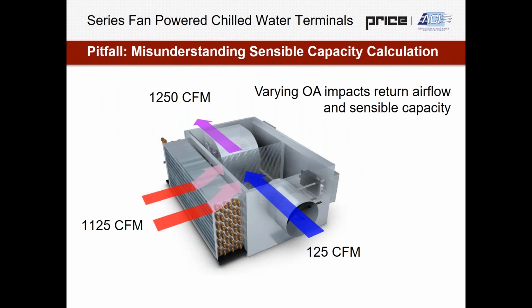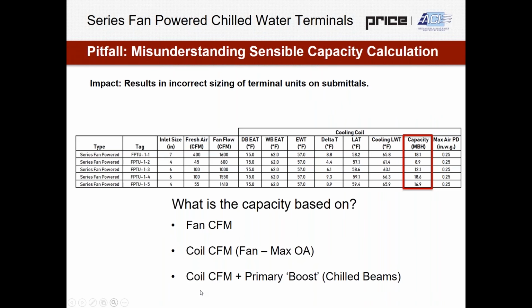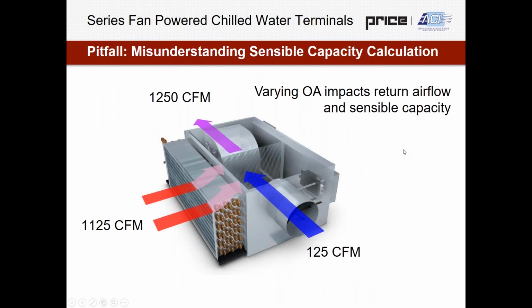So the reason why these things get confused and conflated is because of the way this equipment operates. As the primary air changes and the fan air is held constant, the amount of airflow going through this coil also changes. So that's why it's a bit of a misnomer, or a little bit incorrect, when at times we'd see this capacity calculated with respect to the fan flow that's operating. So an assumption of 1600 CFM through this coil would be incorrect, while an assumption of 1600 less 400, or 1200 CFM, through this coil would be much more optimal and ideal.